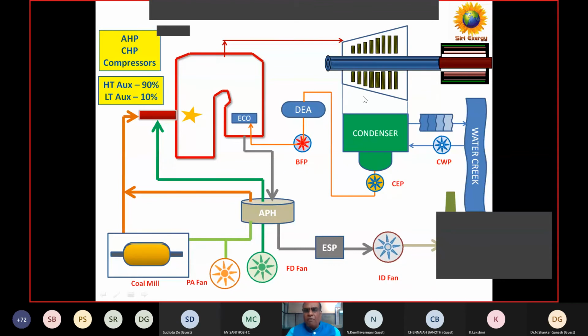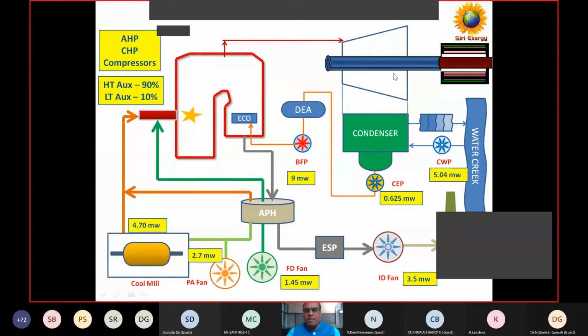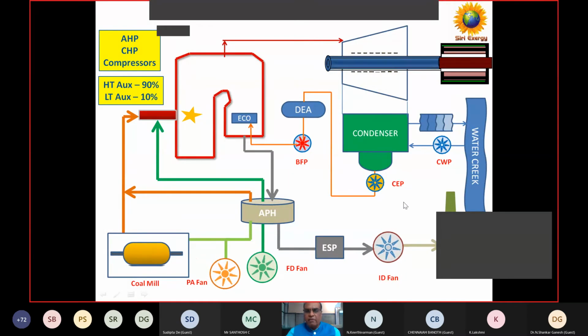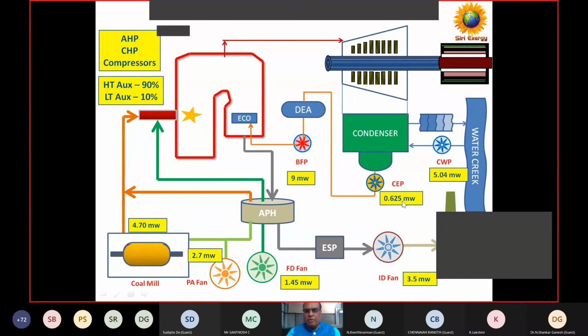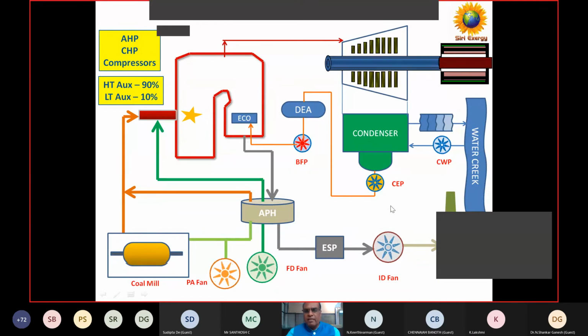After the condenser, wherever the power generation happens, whether HP turbine, IP turbine or LP turbine, there is a condenser, and after that the condenser extraction pump, CEP, consumes almost 300 kW per pump, with two pumps running it's around 600 kW. Then, to cool the condenser, we have to supply cooling water.